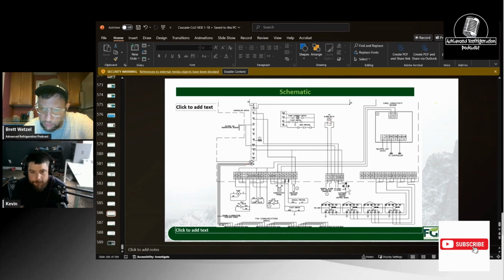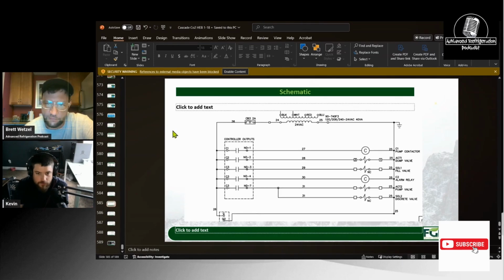Right down here, you can run these fans off of 4 to 20, 0 to 10, or 10 to 0, and then there's your general alarm output relay that you can use for a DI on your main BMS controller. And then every other thing on here, pre-cool, float switch, I believe everything here is 120. Yeah, because there's another transformer, because it steps it down from 480 to 120 to 24 volts, I believe. Yeah. So, oh no, never mind. So the dump valve, the fill valve, pump valve, discrete valve, all that should be 24 volt AC.